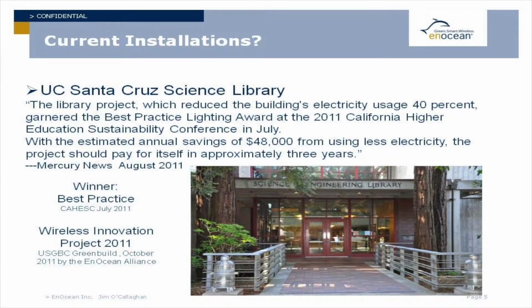A couple of case studies—this is a current installation at the UC Santa Cruz Library, their science and engineering library. It reduced the entire building's energy consumption by 40%, not just the lighting circuitry, but completely by 40%. I believe this one had some funding from PG&E, and their estimated annual energy savings are $48,000, so they estimate it will pay for itself in 2.65 years. It's a great project, a beautiful building, with 2,200 light fixtures being controlled by occupancy sensors and relays, with no upper level building management system—it's all done locally.